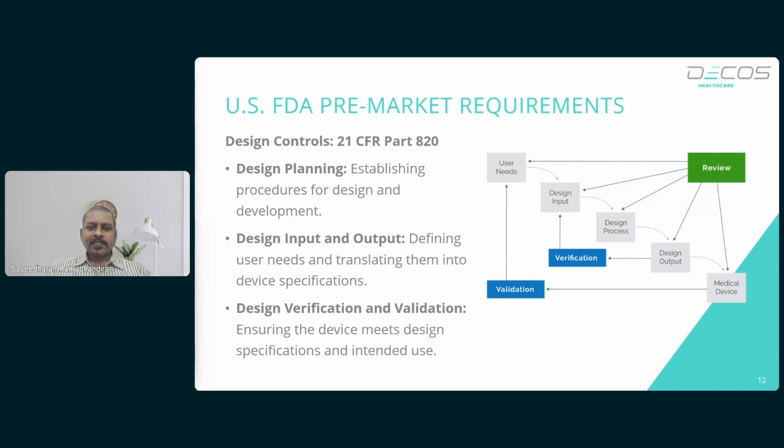To talk about US FDA's pre-market requirements, the FDA requires manufacturers to adhere to a structured framework for device design, risk management, and clinical evidence collection. Design controls must be compliant with 21 CFR Part 820, with the following structure, where the key components are design planning, design input and output, design verification, and design validation.